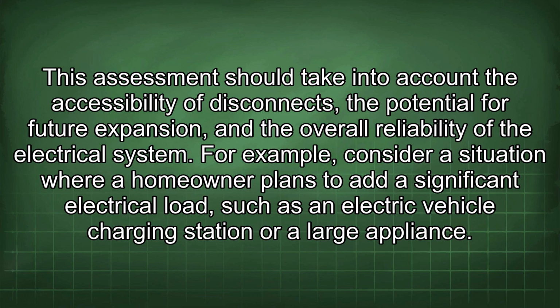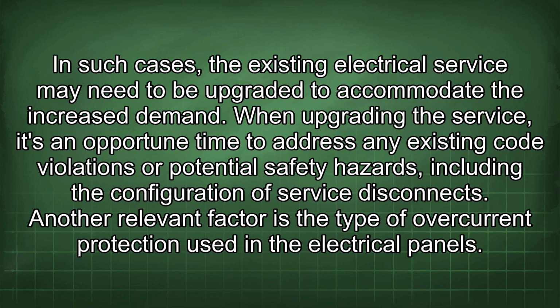For example, consider a situation where a homeowner plans to add a significant electrical load, such as an electric vehicle charging station or a large appliance. In such cases, the existing electrical service may need to be upgraded to accommodate the increased demand. When upgrading the service, it's an opportune time to address any existing code violations or potential safety hazards, including the configuration of service disconnect.